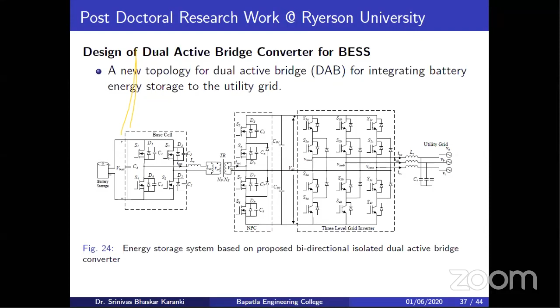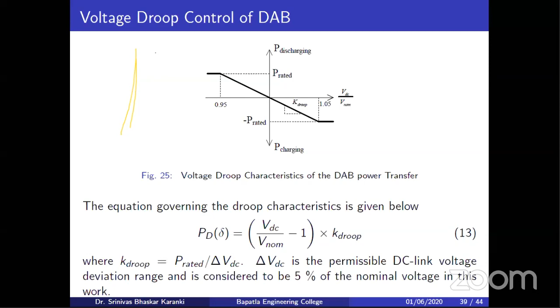We have used droop control to control the angle delta. If the battery is below the required level and grid power is sufficient, charge the battery. If the grid needs power, give power from the battery. That is what the droop control does.